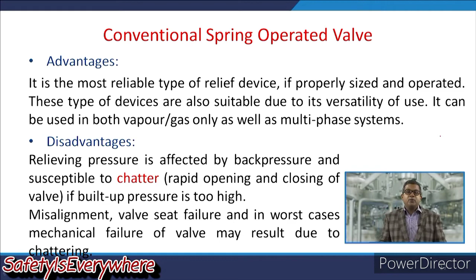While we have the advantages, there are certain disadvantages also associated with these conventional spring operated valves. The relieving pressure is affected by back pressure, and the valve is susceptible to chatter, that is the rapid opening and closing of the valve. If the built up pressure is too high, misalignment of the valve seat may occur, and in the worst case, mechanical failure of the valve may result due to chattering. So this is the disadvantage associated with the conventional spring operated valve.